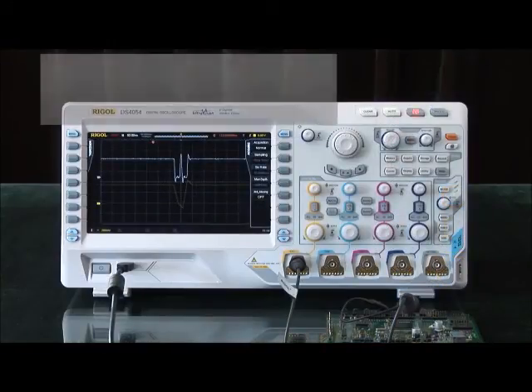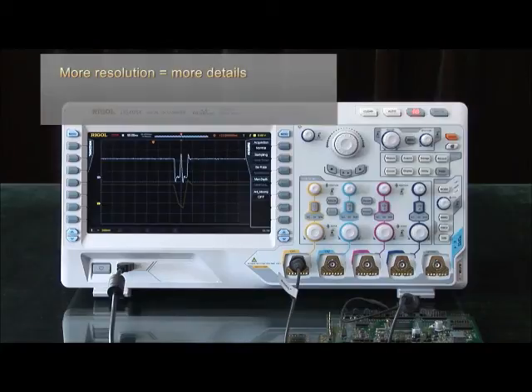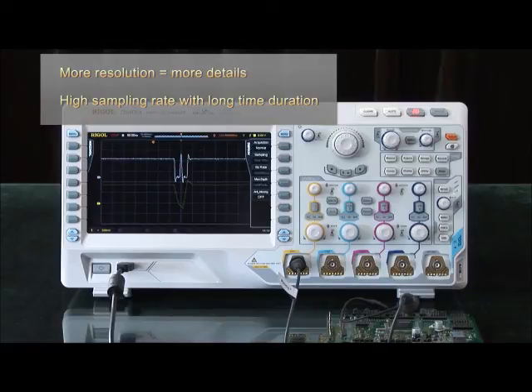In conclusion, deep memory provides more resolution that leads to more details in each of your waveforms. It also allows you to have a high sampling rate with long time duration, which allows you to capture more of a signal for every triggered event.